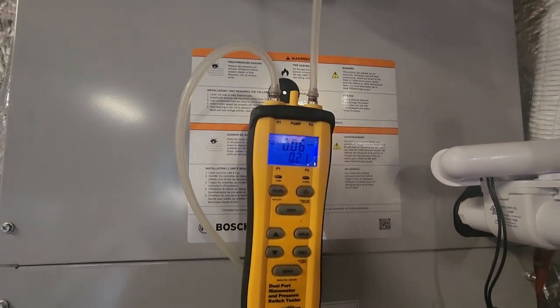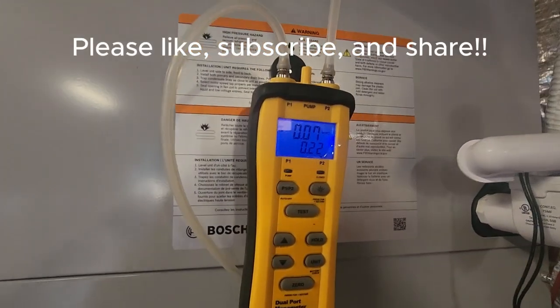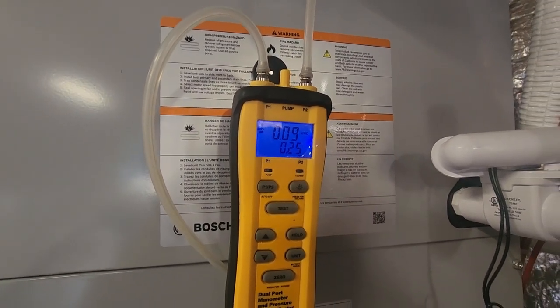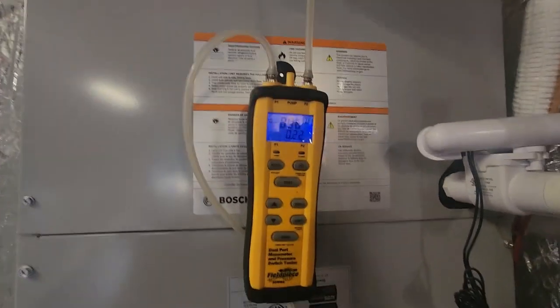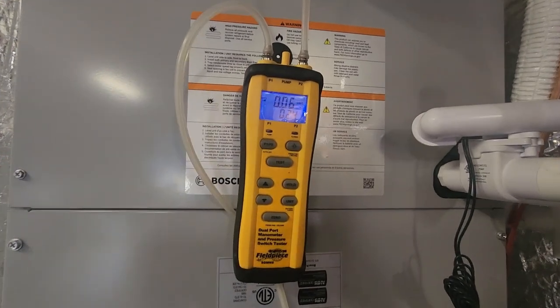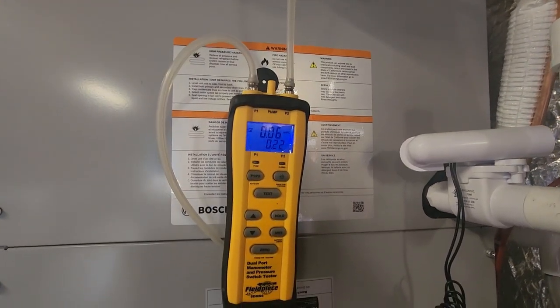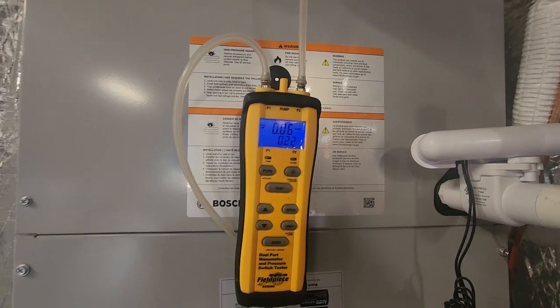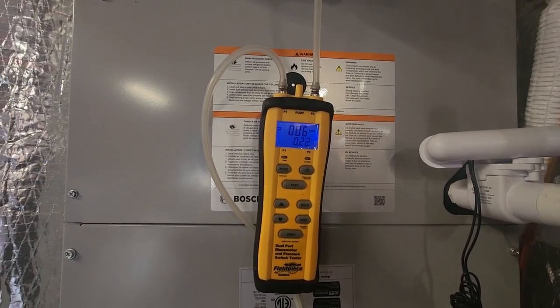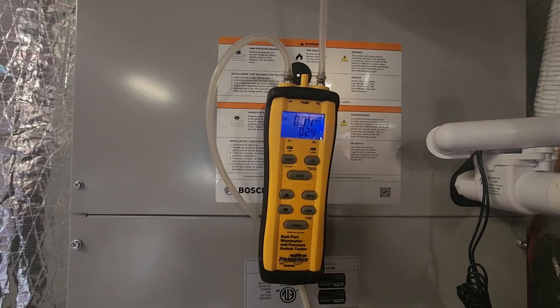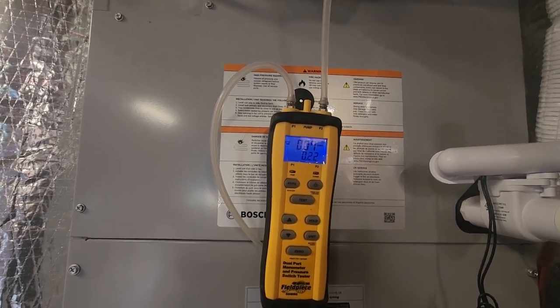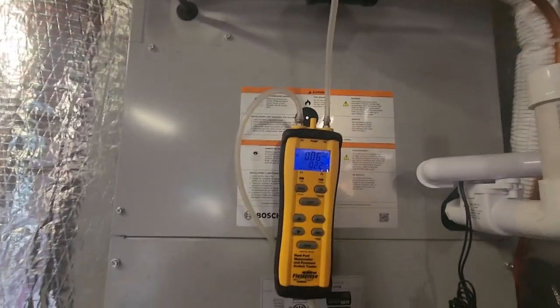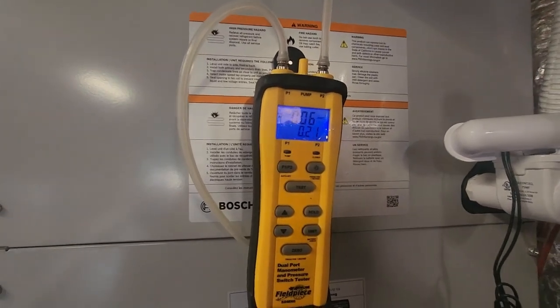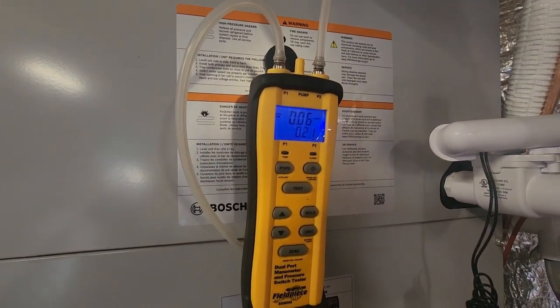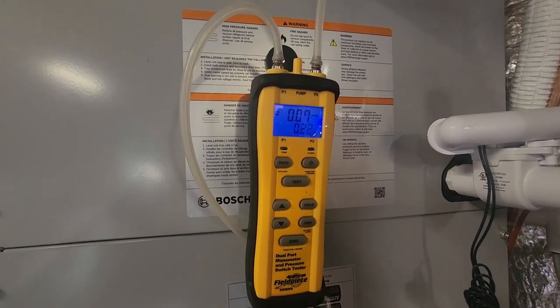Let's do second stage. Let's open them both up and see what our static is without the filter in, and that'll conclude this static pressure test, which is awesome. All manufacturers put what their recommended maximum static is. On these, it's 0.8, I believe. We strive for 0.5, but man, this thing's getting awesome airflow, and it's going to last me a long time. Keep this filter clean in there. Oh man, I'm loving my system right now. I never get this when I test these on customers' jobs because I haven't messed with the ductwork. I did all this ductwork on this house.